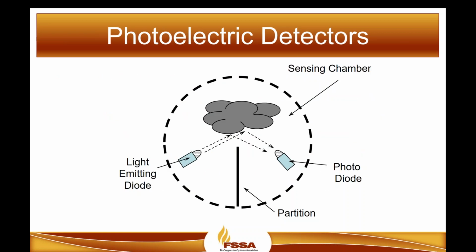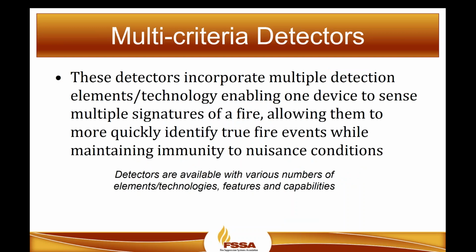Yeah, this has been the most widely used smoke detector in special hazard smoke detection for many years now. It performs better in high airflow environments than the traditional ionization, and its early warning capabilities make it much more responsive to a smoldering fire or products of decomposition coming off of failure of parts. It can be susceptible to contaminants such as refrigerants causing false alarms, and debris, but the industry's done a very fine job utilizing chemically etched screens that won't let any large particulates obstruct the photoelectric sensing chamber. So they've been really, really stable. Thanks, Jeff.